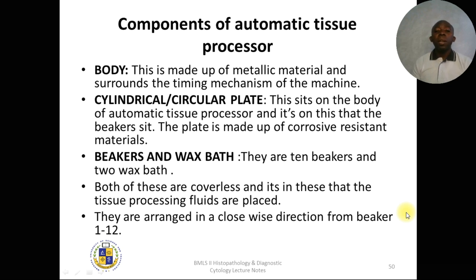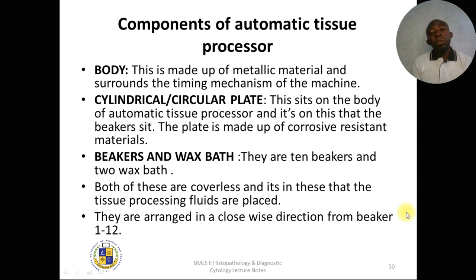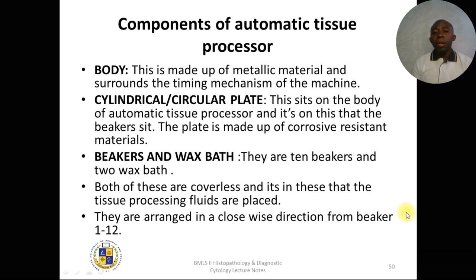The wax baths contain the infiltrating reagent — molten wax — and must be kept at a temperature high enough to keep the wax molten so it can penetrate the tissue well. They are identifiable on the tissue processor as metallic, non-transparent containers attached to electric heaters. It is in the wax baths that infiltration takes place.